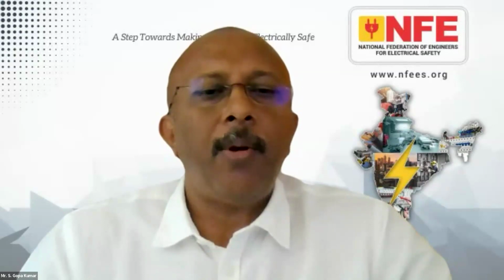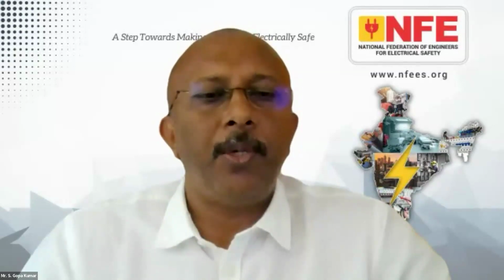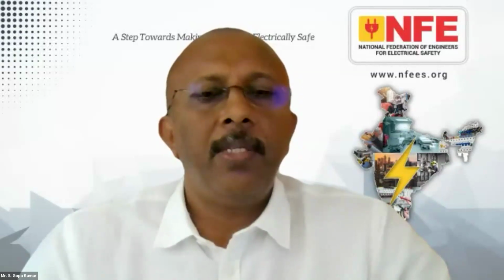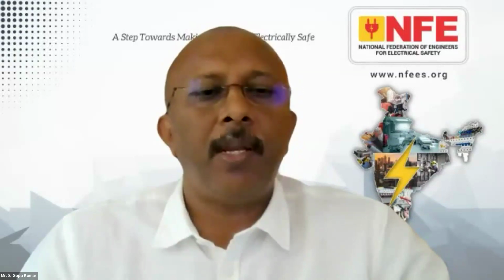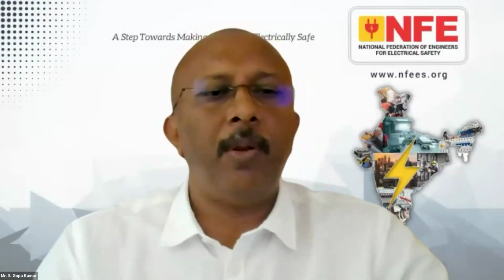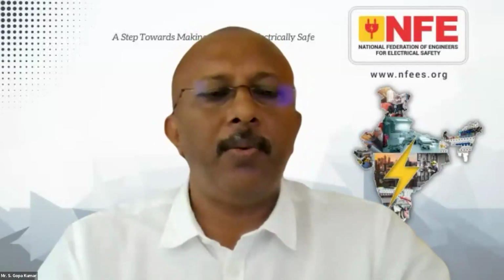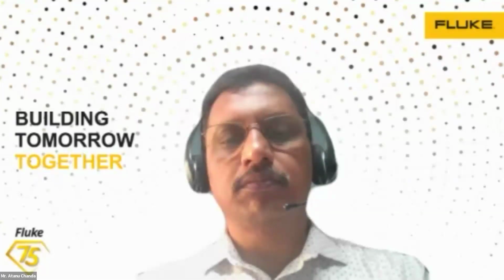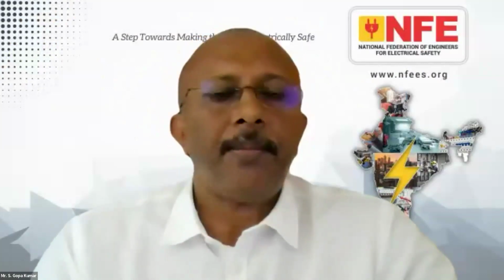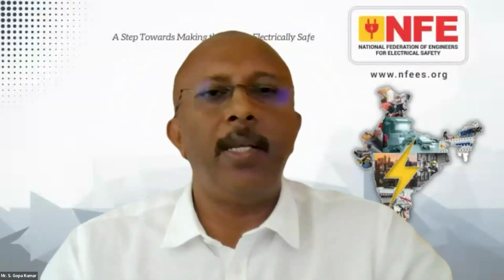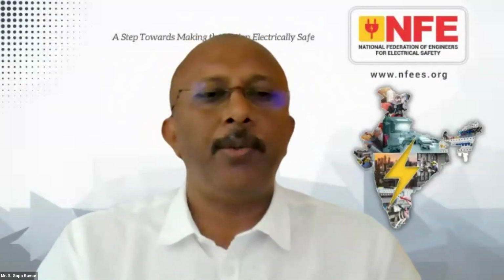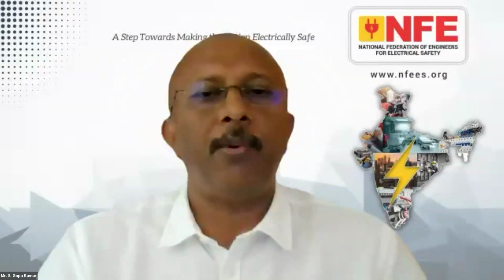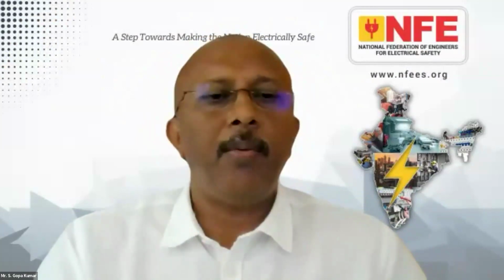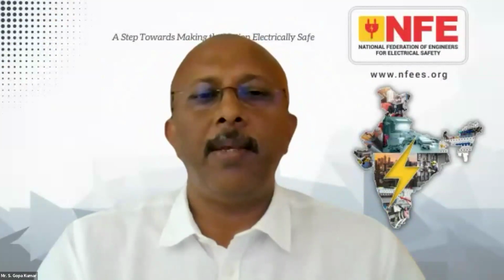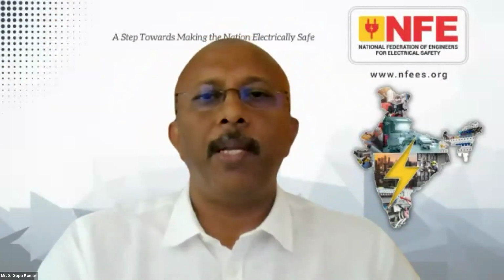Not even one earth electrode is required for protecting people from shock and protecting your electrical installation against arcing. Since not even one is required, we can just forget about multiple earth electrodes, up to 1000 volt AC, 1500 volt DC. If you have confusion, please download IS 732 and IS 3043 — these are very good technical documents with a lot of information. I hope my answer is clear.